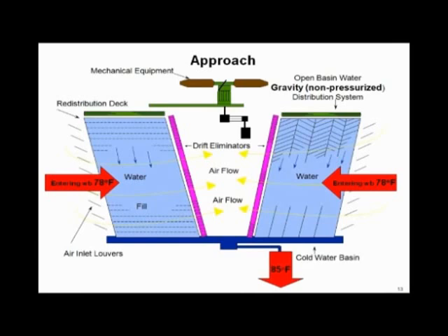So you're saying to me, Chris, for every ton of load on my cooling tower, I'm going to evaporate 15 pounds of water. Absolutely. Let's keep it simple. That's exactly what you're going to do. You're going to have rocks left behind, by the way, which we'll talk about later on. But you're going to have to do that. So now I'm making 85-degree water, and what's my approach? My approach becomes 7 degrees. And that's what I want to make sure you understand.